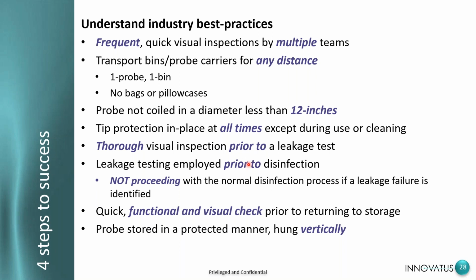If we look at some of the methods of high-level disinfection out there, there are some passive soaks where the probe is in for 10 or 12 minutes, and if we have a pinhole, it may not be so bad. But then there's a piece of equipment I've seen called the Medivator, which is a really cool name, by the way. It is like a high-tech dishwasher that uses high-pressure fluid to disinfect scopes and TE probes, and that will force fluid into the smallest breach of a probe. So we want to do the electrical leakage test prior to any type of disinfection. As I mentioned earlier, the leakage test is great for two things: patient safety and identifying a breach in the probe.